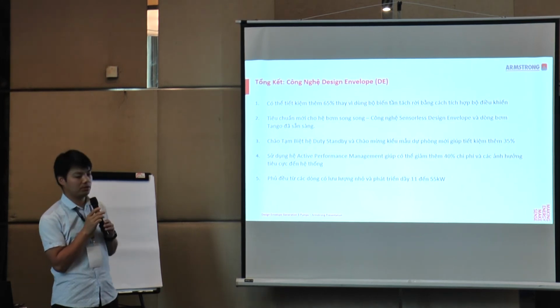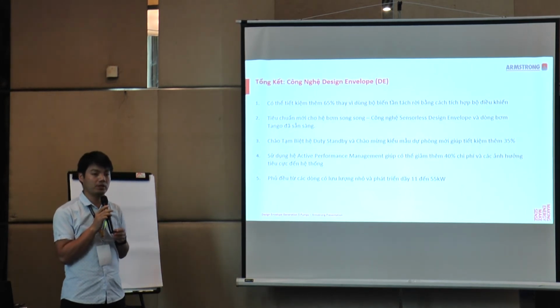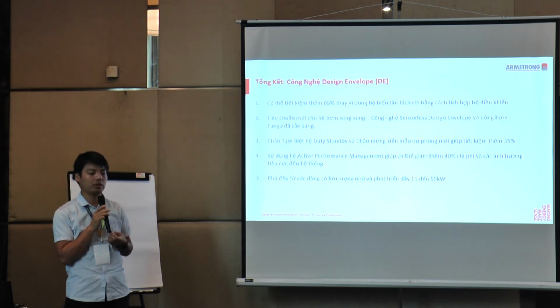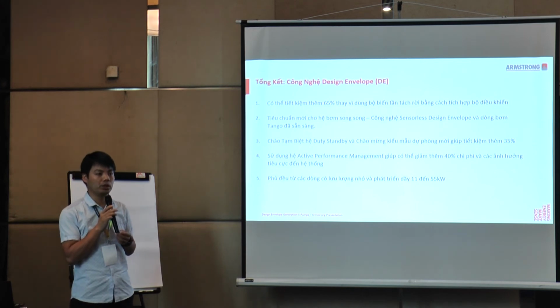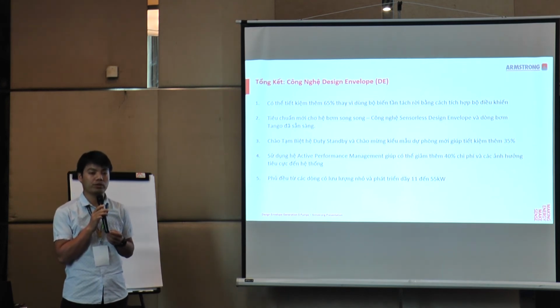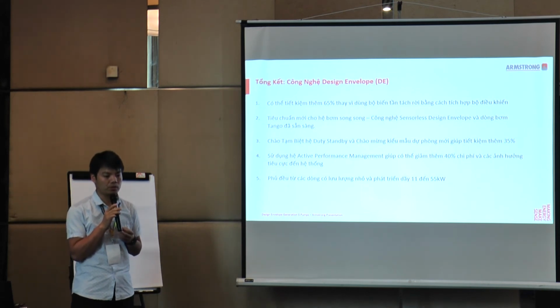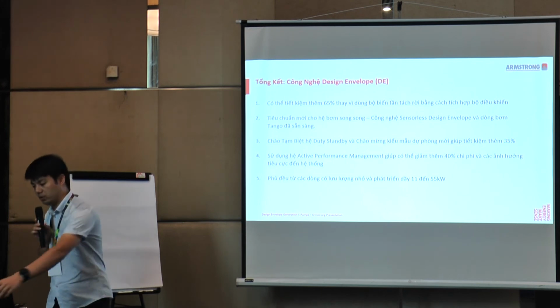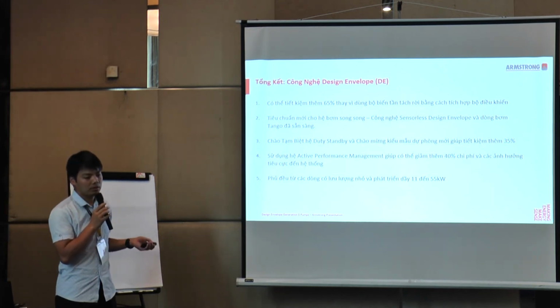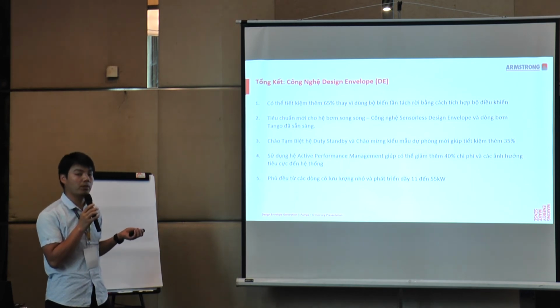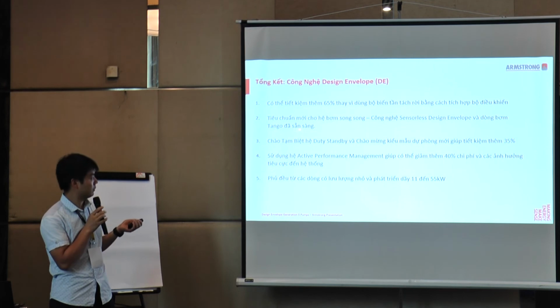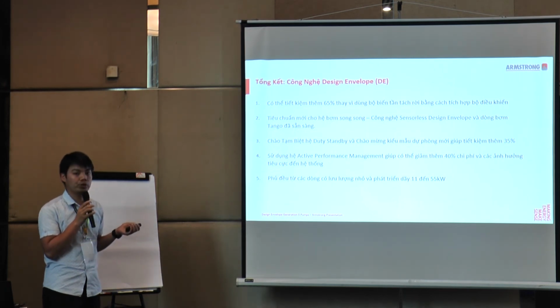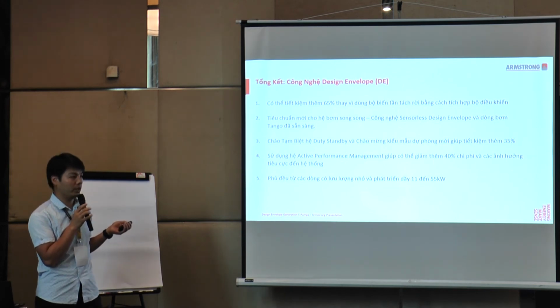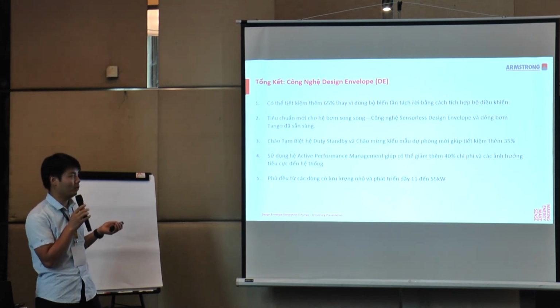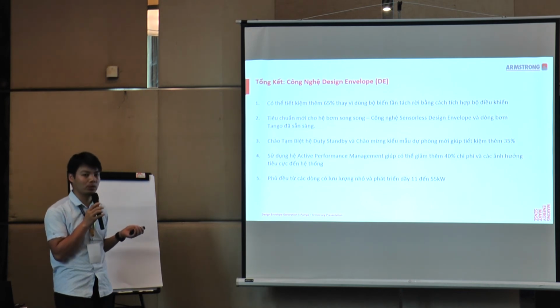Then we talk about these sessions. The first one is the energy savings. It will achieve 65% savings compared to the induction motors with IE3 and also the separate VFD installations. And the second one, we introduced our sensorless Tango pump with sensorless technology embedded. And the third one, we introduced the redundancy concept, so we can say goodbye to the duty standby concept and say hello to the redundancy concept for the new design.